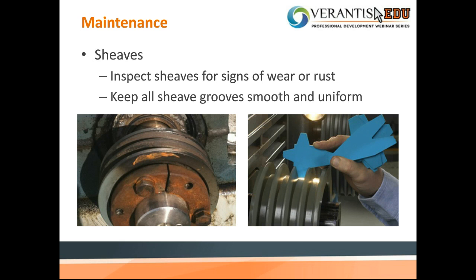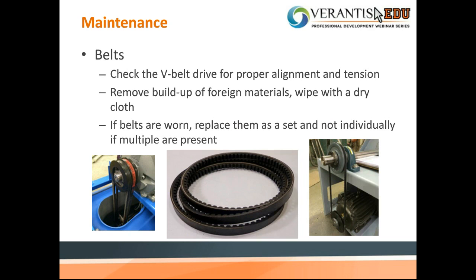So the next one, belts. Check the V-belt drive for proper alignment, just like we talked about at the beginning. Remove foreign material from the belt and wipe dry with a cloth. If belts are worn, replace them as a set and not individually. If you replace them individually, they wear at different periods of time.